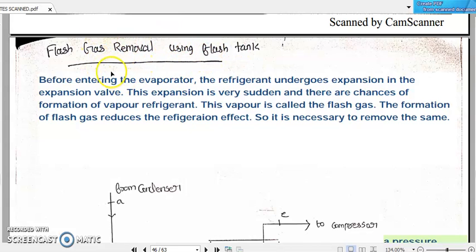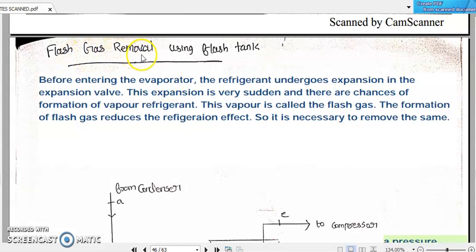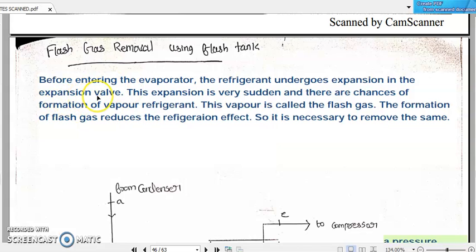One important term is flash gas removal using a flash tank. What is this flash gas, why does it need to be removed, and what is a flash tank? Before entering the evaporator, the refrigerant undergoes expansion in the expansion valve — that is, the throttle valve — as we already learned in our standard VCRs.